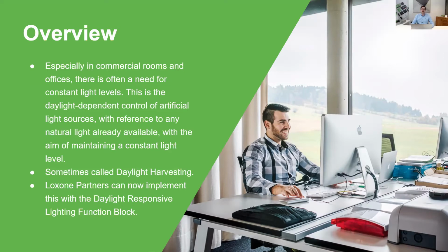However, you go and open up a set of blinds in an office, and you've got potentially on a summer's day a lot of sunshine coming in and a lot of natural light entering that room. And so that's why there's different names for it, like daylight harvesting or responsive lighting control. But what we want to do is dim the lights in the room or brighten them depending on how much ambient light is getting into the room from the outside world, so that we're always maintaining 600 lux at the desk, and that the dimming up or down of the lights in the room is very, very smooth and not that noticeable for the employees, but we're always maintaining 600 lux.